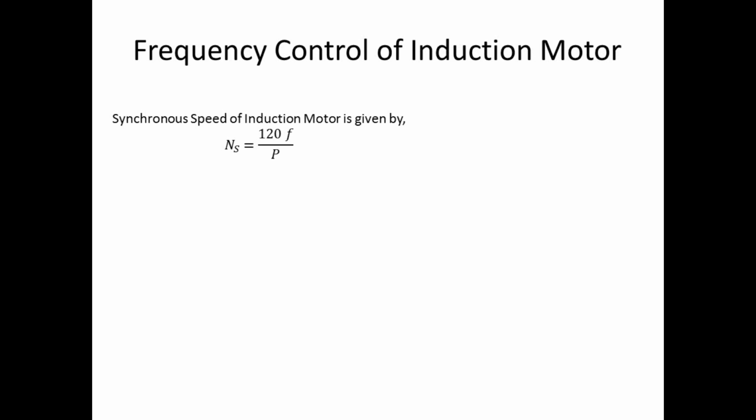So it is clear that the synchronous speed is depending upon the supply frequency. So we can say that if the supply frequency is changed, we can vary the synchronous speed. And obviously if synchronous speed is varied, we can vary the rotor speed. So we can control the speed of induction motor by varying frequency.